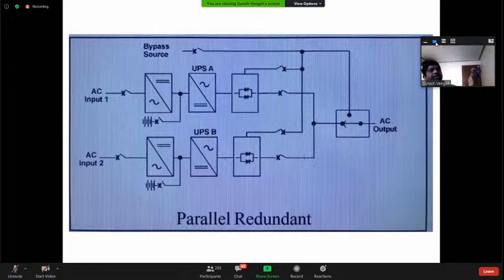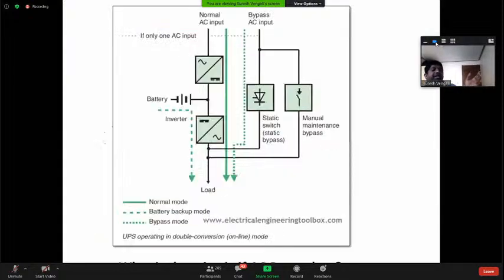You need to specify the equipment in another room. One more thing is, when you specify the battery, you cannot keep the battery in the same room, because batteries are very sensitive. If any damage comes, your UPS will be impacted. So batteries should be a little far, and you need to take care with maintenance and all.